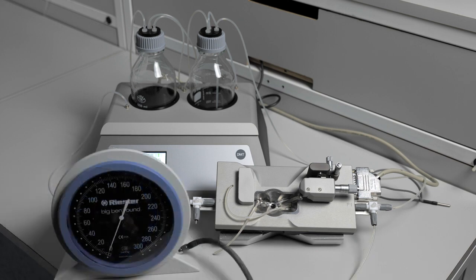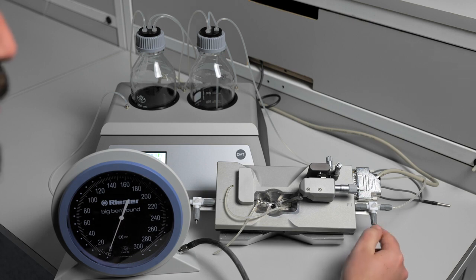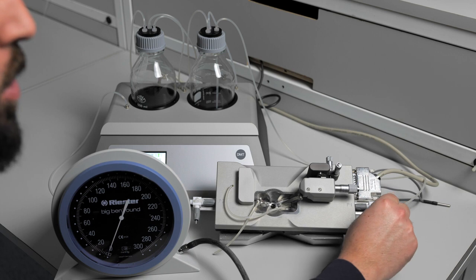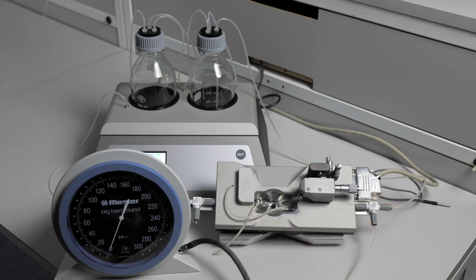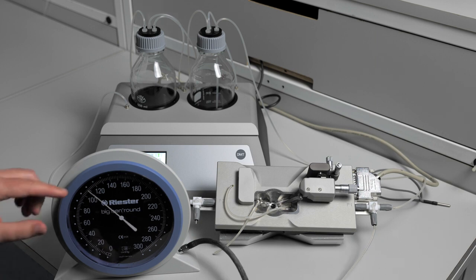The three-way valves on the pressure chamber can be broken if the chamber is accidentally bumped into the bench or the microscope or anything else. If you think you have a leak in the three-way valve, you should connect the Big Ben Round manometer to an open port and then close the three-way valve to that port. Add pressure and it should hold very steady. If it does, then the internal seal is still good, and that is not the cause of your leak.